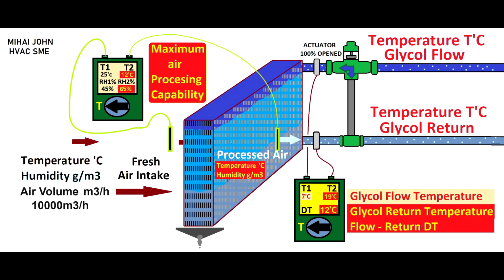Unlike in the other situation, this scenario appeared to indicate a potential fault related to the AHU system. If the fresh air intake temperature and the air volume are within the AHU's maximum air processing capacity, further investigation is warranted. Particular attention should be given to instances where the temperature differential in the glycol flow and return remains high despite the glycol valve being fully open. In such circumstances, it's advisable for the AHU engineer to liaise with the chiller engineer responsible for glycol flow.